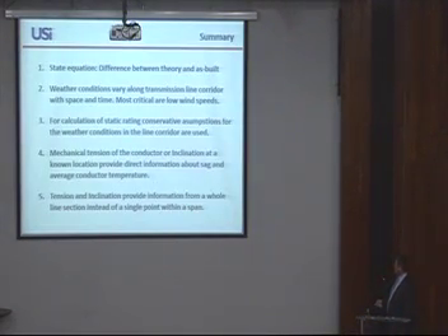So the tension and inclination provide the information from a whole line section. This is a difference to what we in CIGRE are calling point measurements. A point measurement would be a weather station or the measurement of a conductor temperature at a single point. These two parameters are distributed measurements along the line sections. And if you look into the CIGRE TB 498, I think it's in it, dealing with dynamic line rating, it says that these types of measurements are the most accurate way to determine the conductor condition.